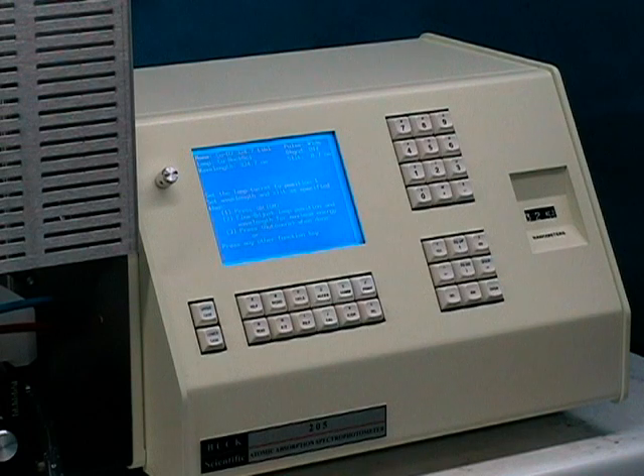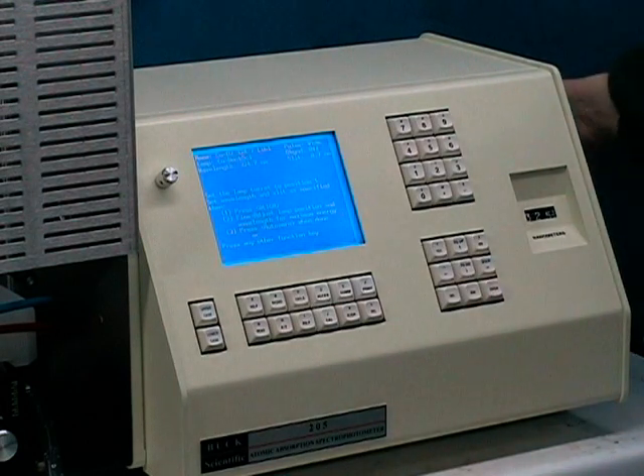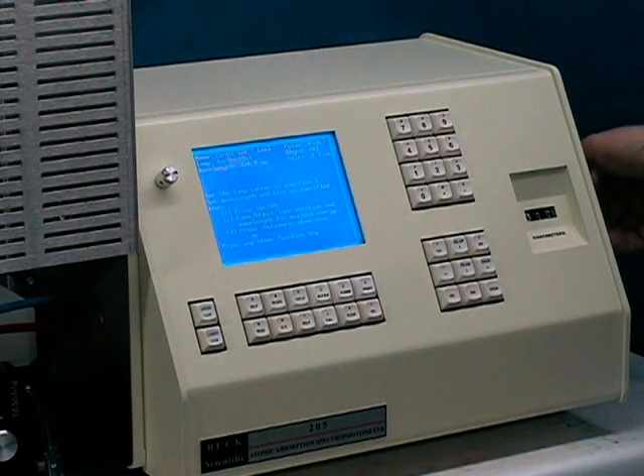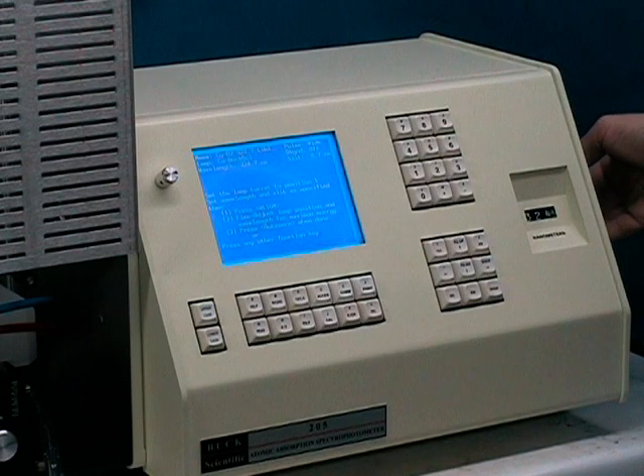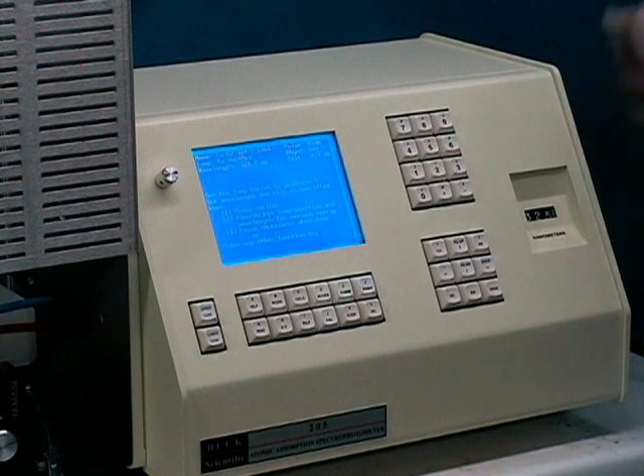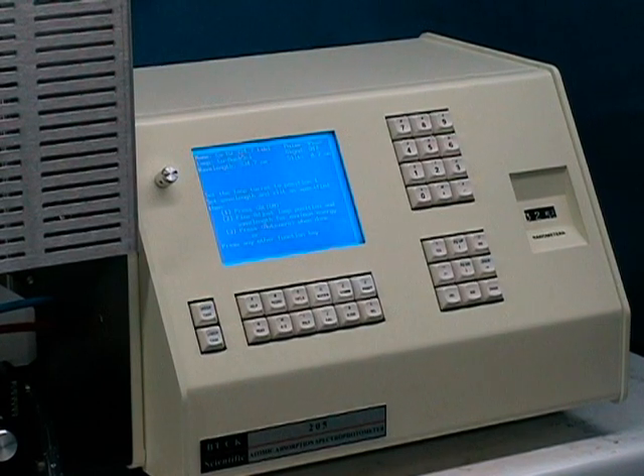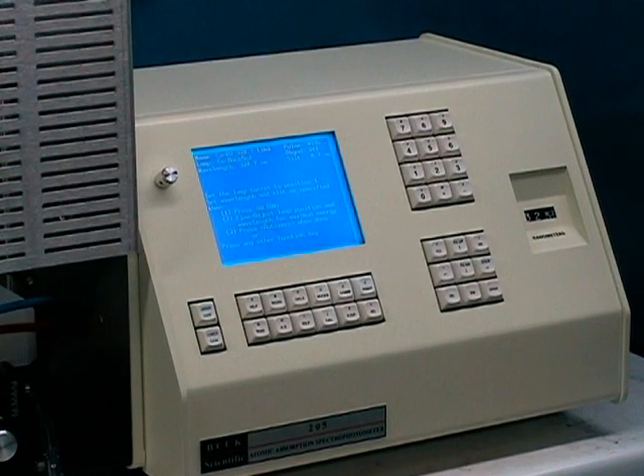As we follow the directions on the alignment screen, you will set the slit size on the right side of the instrument, and also approximately set the wavelength. Please be aware that the wavelength counter is an approximate setting and may have a variation of as much as 1 or 1.5 nanometers from the true wavelength position. Once we insert the hollow cathode lamp and go to the alignment mode, we will use the bar graph and energy readings to actually set the specific wavelength.